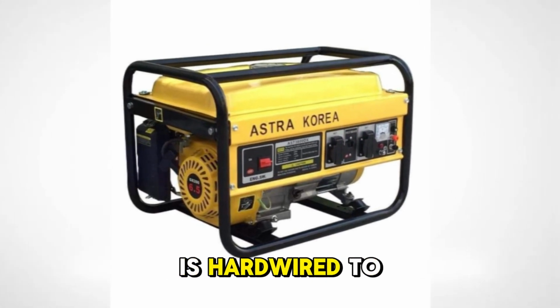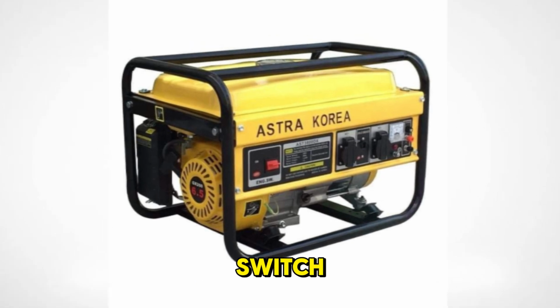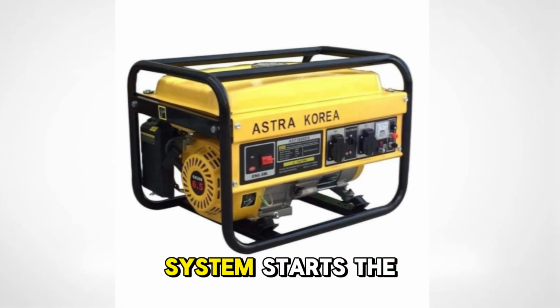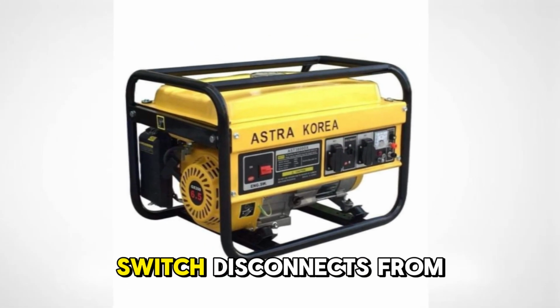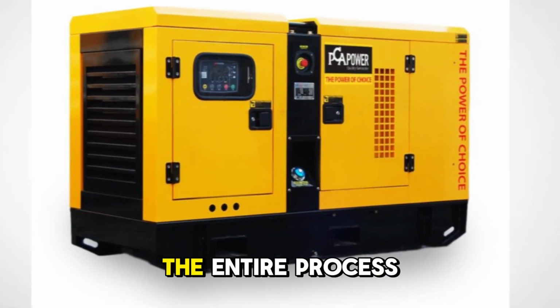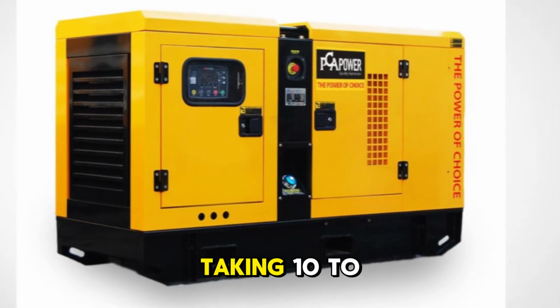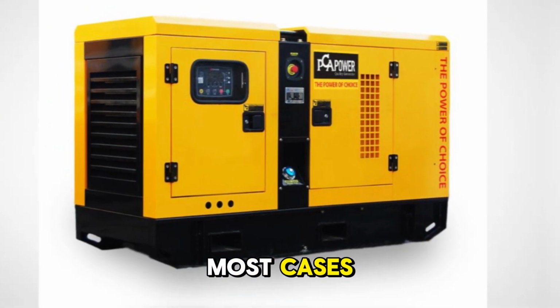The generator is hardwired to an automatic transfer switch. When the power goes out, the system starts the generator, and the transfer switch disconnects from the main grid so that power can safely flow from the generator. The entire process is fast, taking 10 to 15 seconds in most cases.